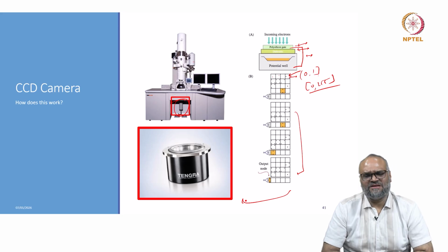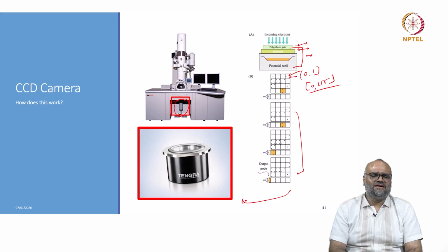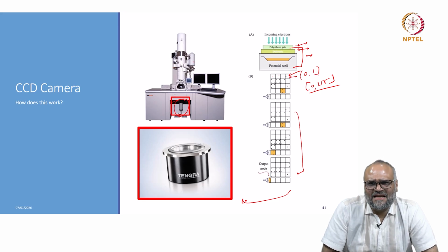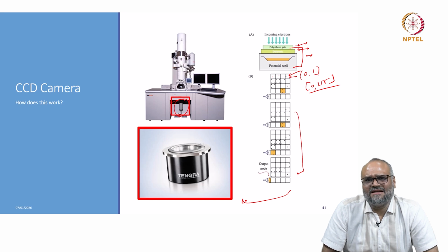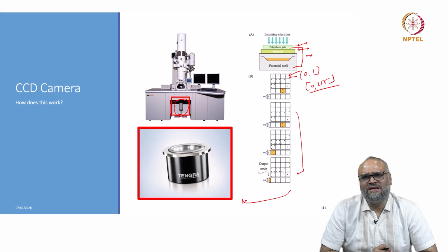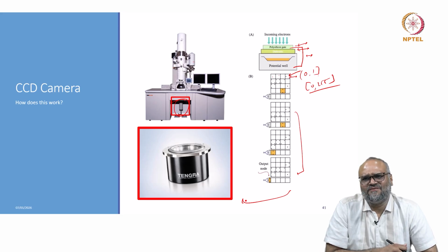And there are some specialized cameras like the K2 and K3, where you also achieve 1600 to even, I think, almost 5000 to 6000 frames per second cameras also available these days. But this is not for the entire size of the detector. When you bin it down, or when you have only a small portion of it, you are achieving higher frame rates.